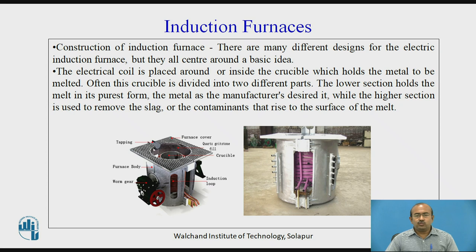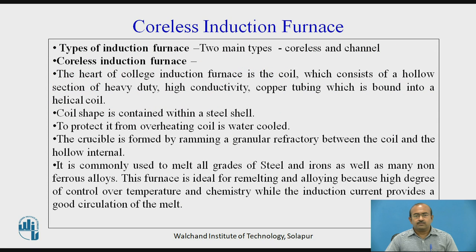Images of actual induction furnaces are shown. There are two main types: coreless and channel. The heart of the coreless induction furnace is the coil, which consists of hollow sections of heavy-duty, high-conductivity copper tubing wound into a helical coil contained within a steel shell. The coil is water cooled to protect it from overheating. The crucible is formed by ramming granular refractory material between the coil and the hollow interior. It is commonly used to melt all grades of steel and iron, as well as many non-ferrous alloys.